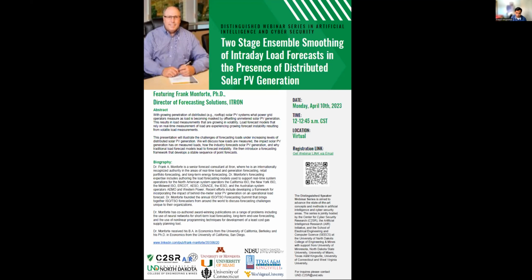To give you a feel for how bad this is looking, in the upper left-hand corner, this is what a full commercial facility looked like before we did anything. Each 5-minute interval of the day is on the horizontal axis, and the vertical bar for any given interval represents 365 days of values, so 365 8 a.m. values. The range really just represents temperature, so air conditioning loads, and there's also a distinction between weekdays and weekends. But that is actually a relatively stable shape for which we could fit some easy models. Down below is how that shape evolves.